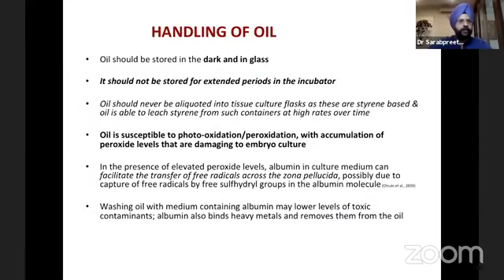A short note on the handling of oil. Oil should be stored in the dark and in glass. It should not be stored for extended periods in the incubator. It should never be aliquoted into tissue culture flasks as they are styrene based, and oil is able to leach styrene from such containers at high rates over time. Oil is susceptible to photo-oxidation or peroxidation, with the accumulation of peroxide levels that are damaging to embryo culture. So please store oil inside the refrigerator, in its original container, and handle it, exposing it to light on a minimum basis.